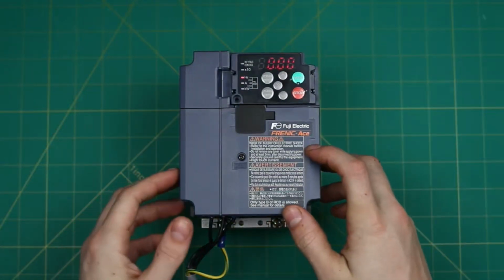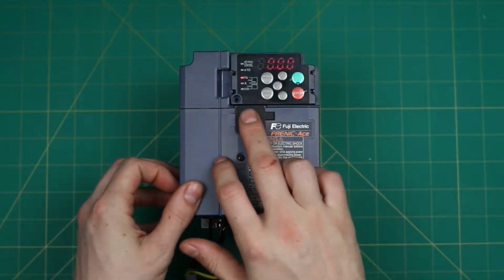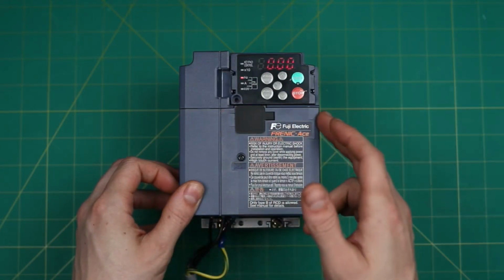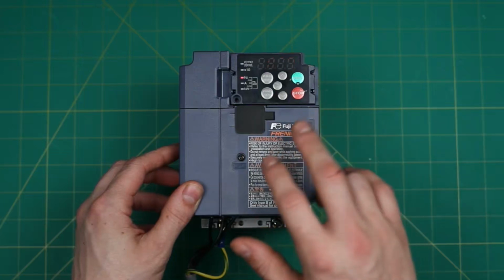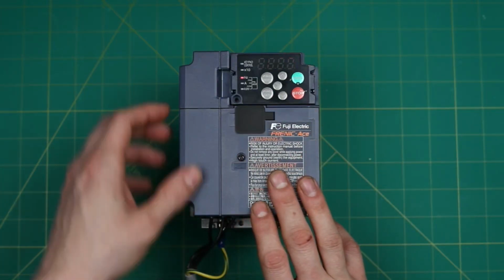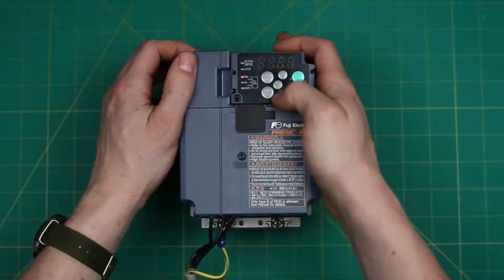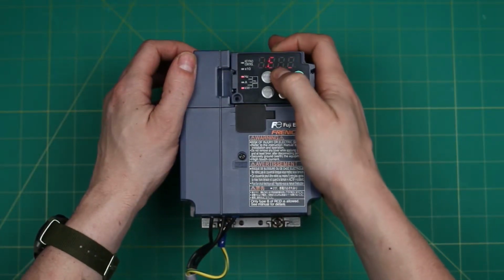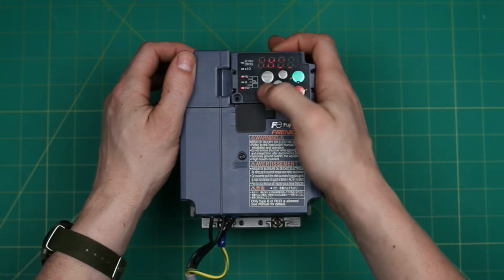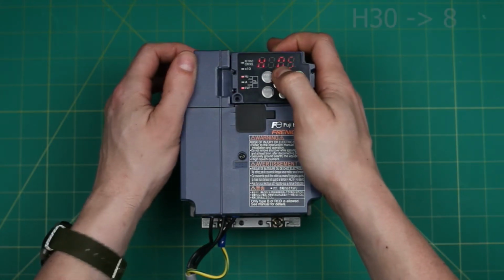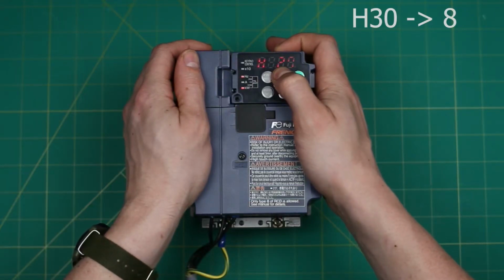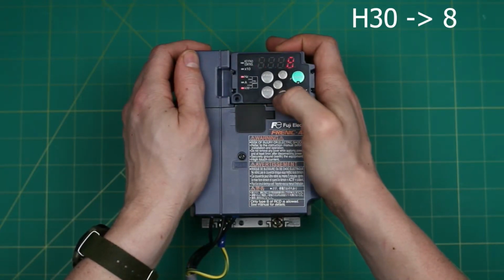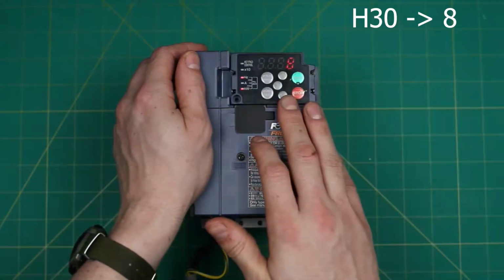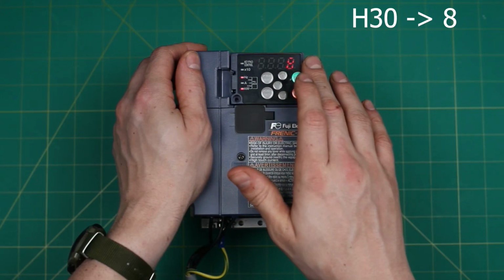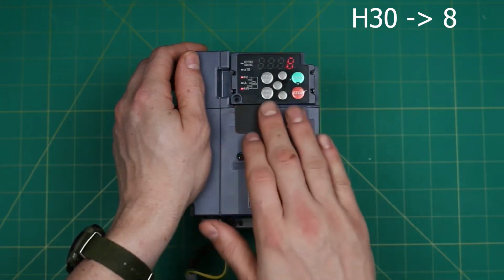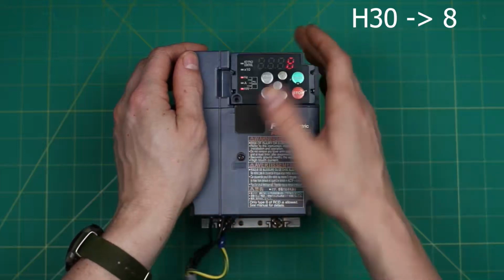Let's start with configuring the VFD. We need to make it so that the COM port 2 on the VFD is able to accept commands, frequency, and run from an exterior source. So, to start, we need to go to Program, and then to H, Function Data. We need to go to H30. Be sure this is set to 8. That sets it to use RS-485 on COM port 2 for frequency and run commands.